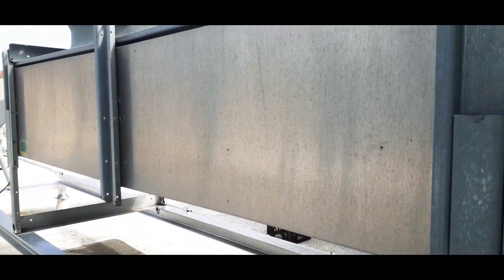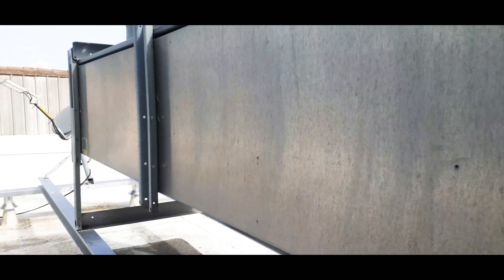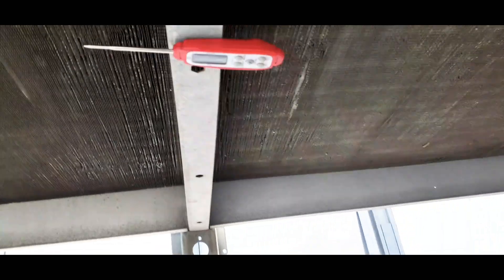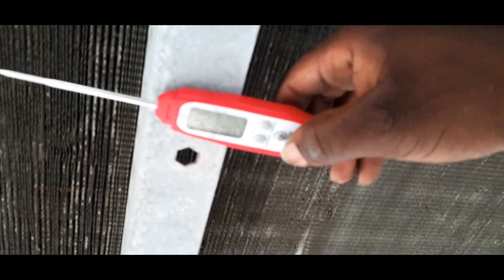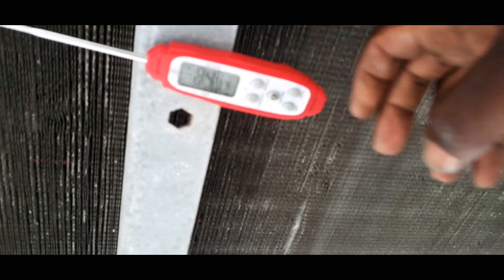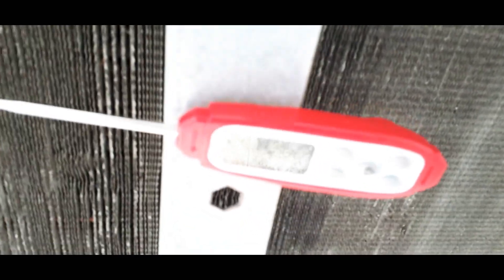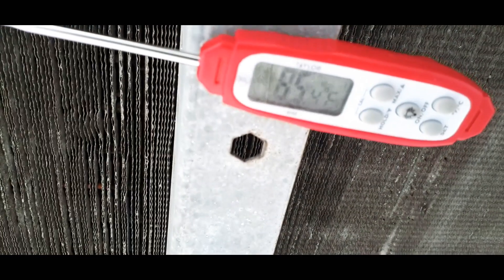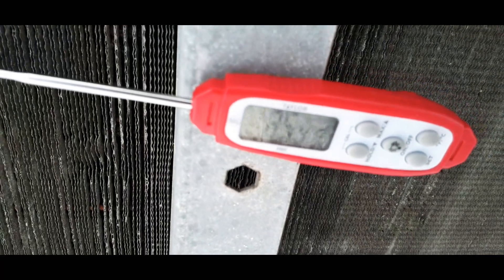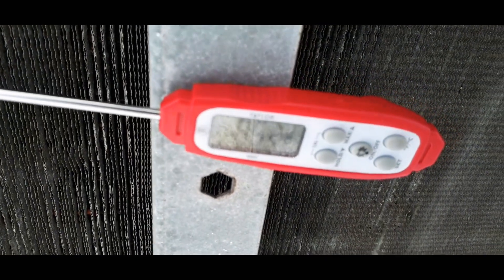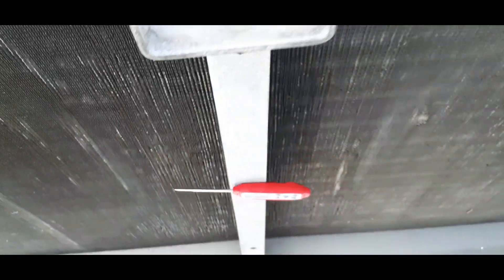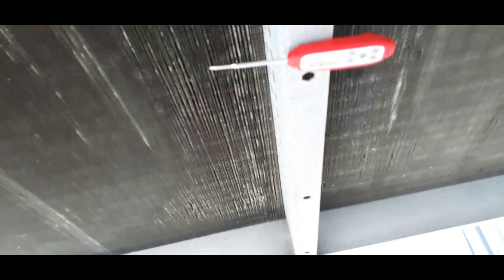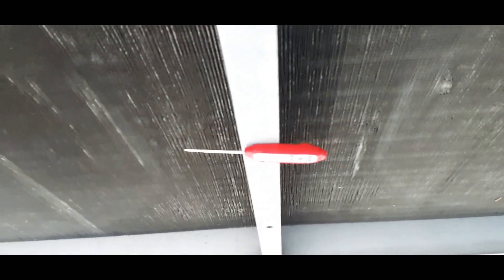Let's just check our temperature right now. Let's see what we're at. So we're at about 85 degrees. If we look at the PT charts, we should be at about 179-180 PSI on our gauge.